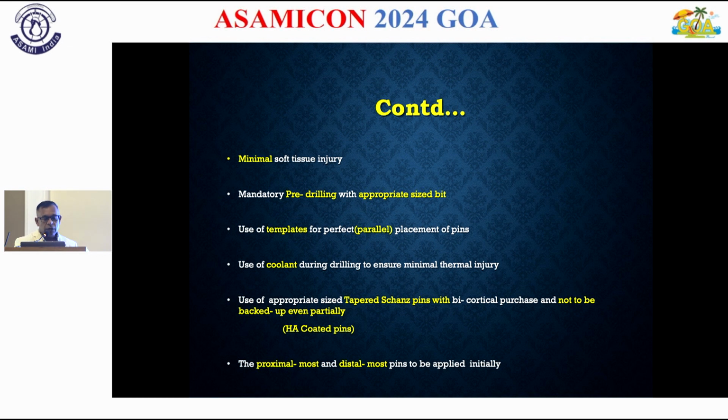Mandatory pre-drilling with appropriate size bit, it goes through for any external fixator. Use of templates for perfect, that is parallel placement of pins according to the bone axis, the long axis of the bone. Use of coolant during drilling to ensure minimal thermal injury. I just want to recall my few days of training under Dr. Milind Chaudhary sir, when I had gone to his center, when I saw him applying an external fixator. The assistant was constantly having a drip in a syringe and pouring it over the drill area till the time the pin was perfectly placed.